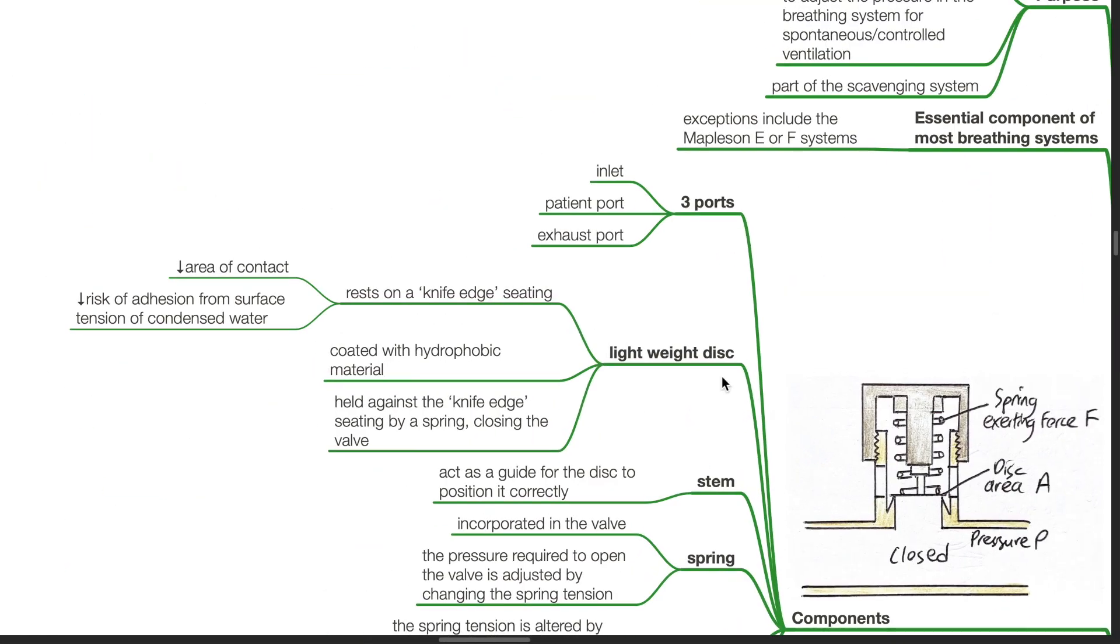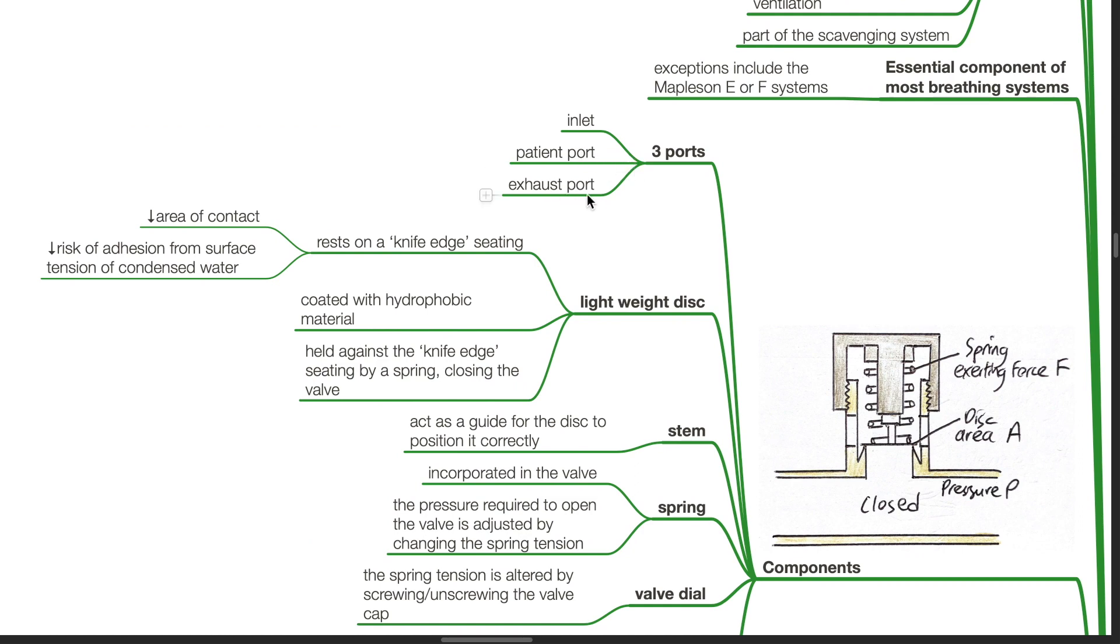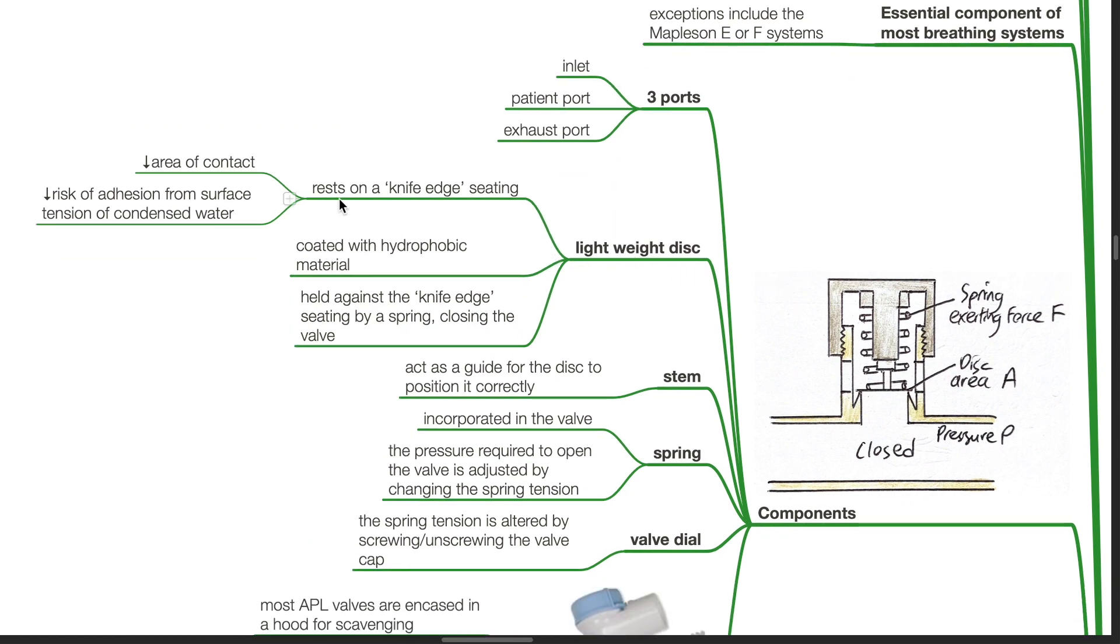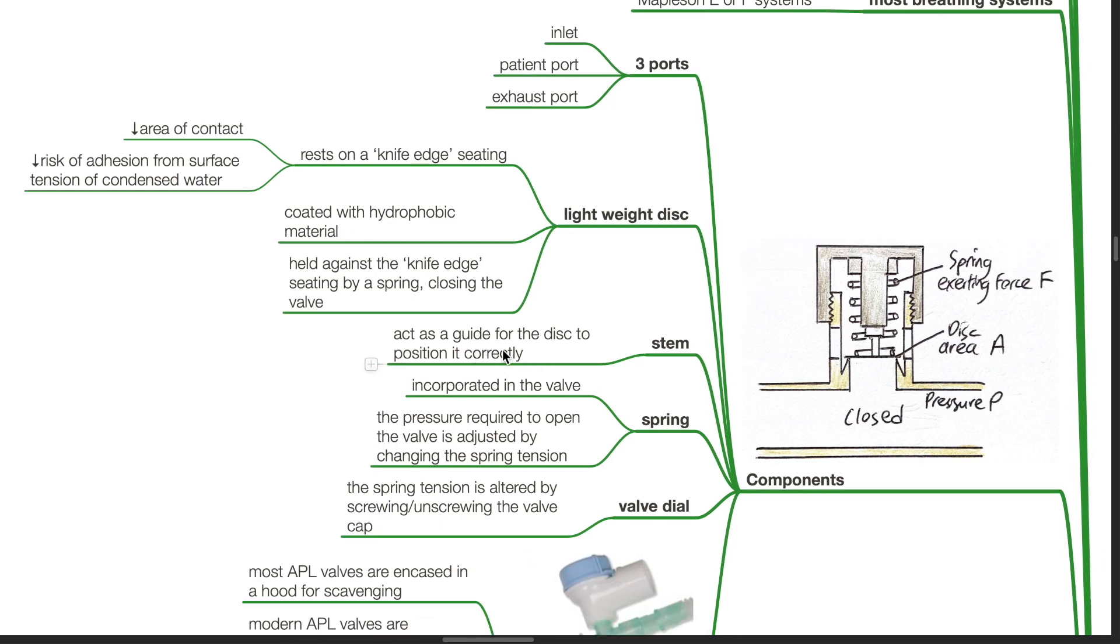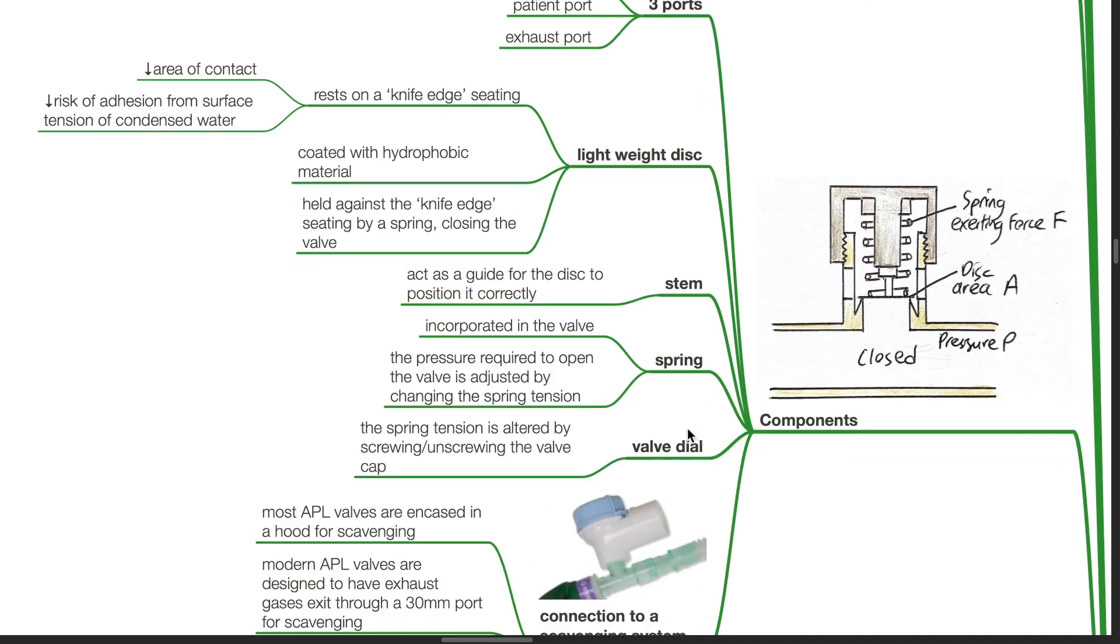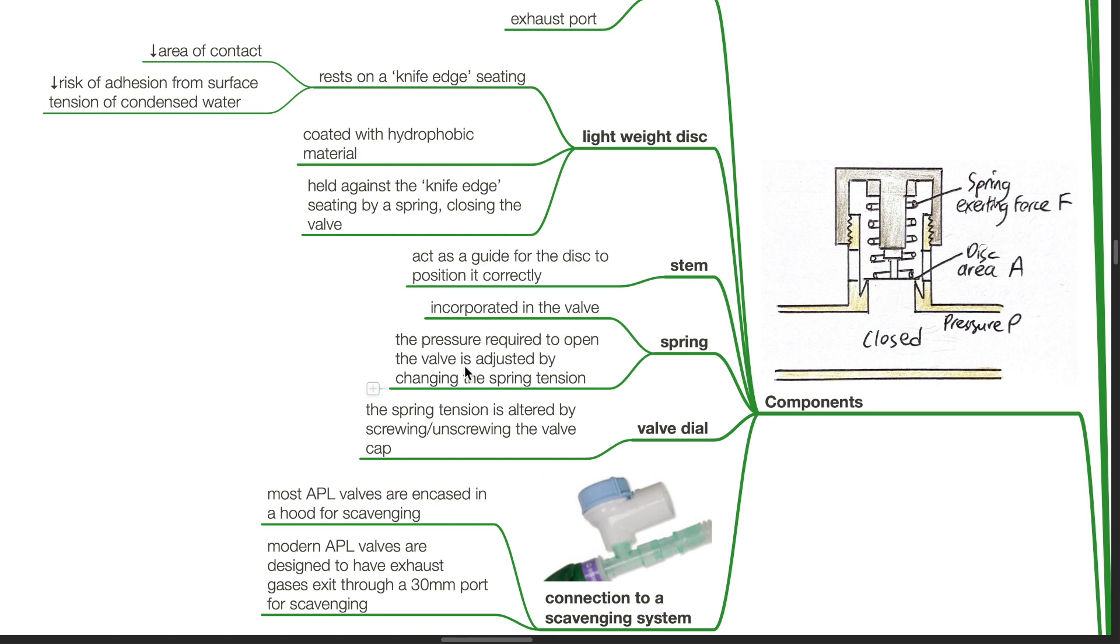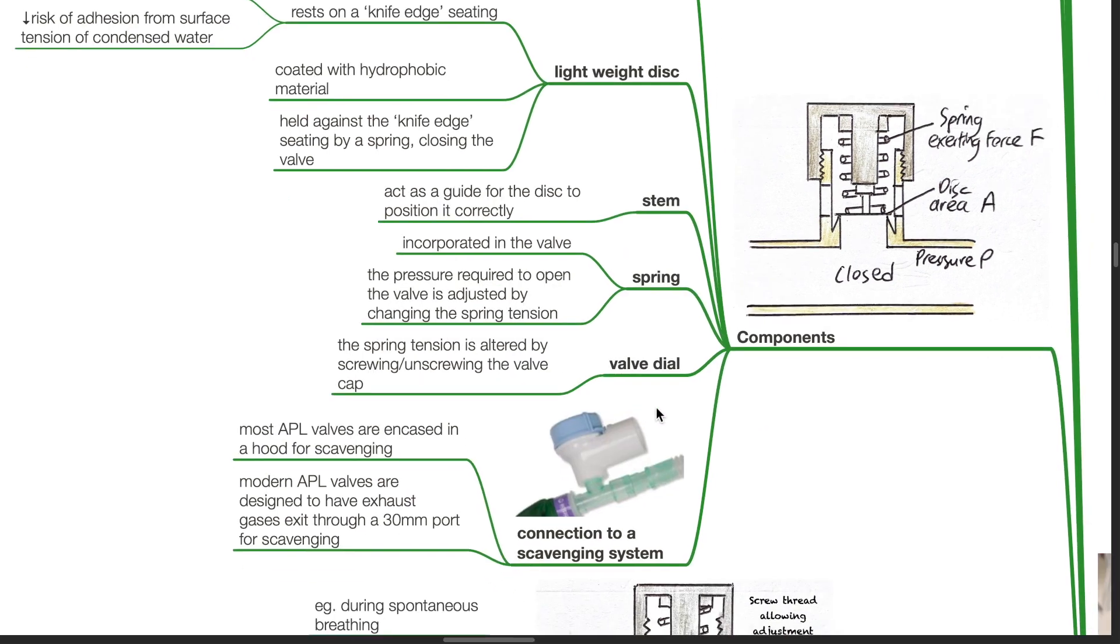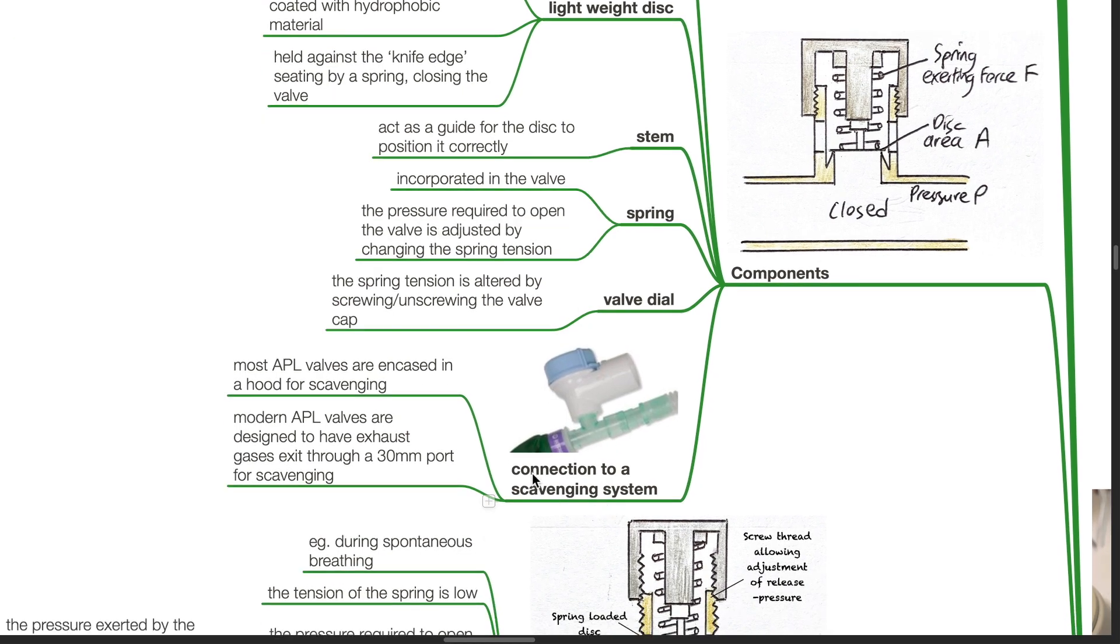Components. It has three ports: the inlet, the patient port and the exhaust port. It has a lightweight disc which rests on a knife-edge seating. This reduces the area of contact and reduces the risk of adhesion from surface tension of condensed water. It is coated with hydrophobic material and held against the knife-edge seating by a spring, closing the valve. The stem acts as a guide for the disc to position it correctly. The spring is incorporated in the valve. The pressure required to open the valve is adjusted by changing the spring tension. The spring tension is altered by screwing or unscrewing the valve dial. It has a connection to a scavenging system. Exhaust gases exit through a 30mm port.